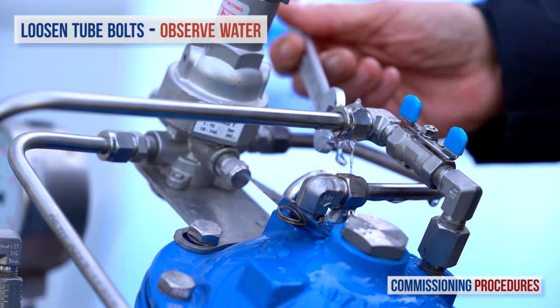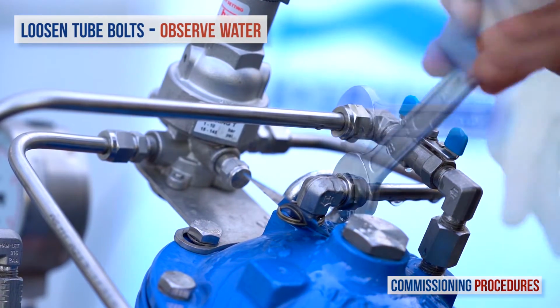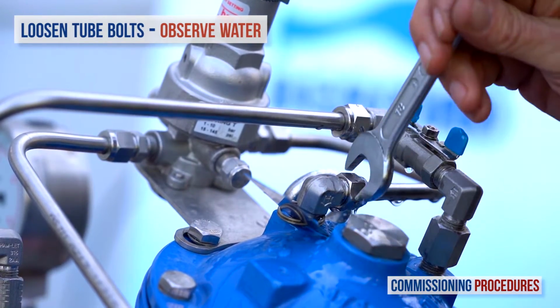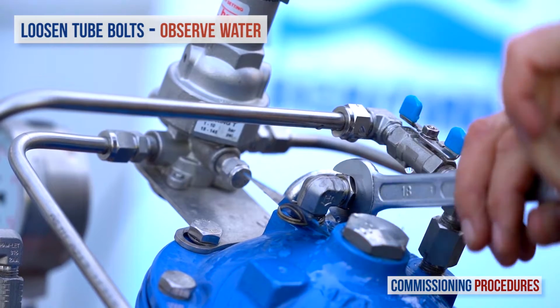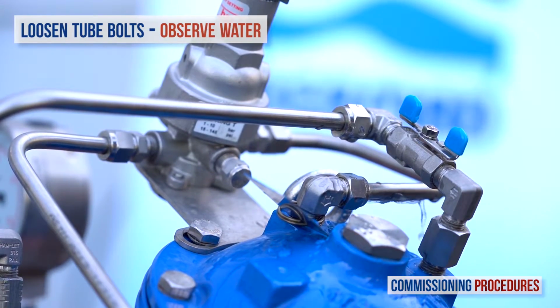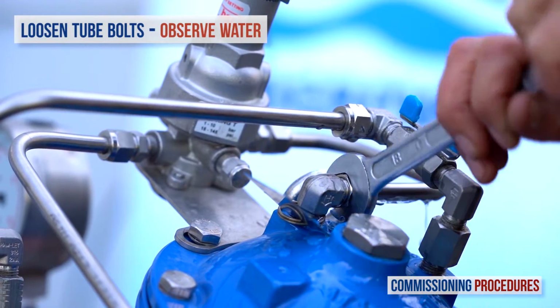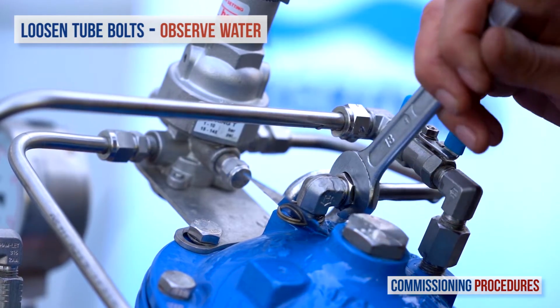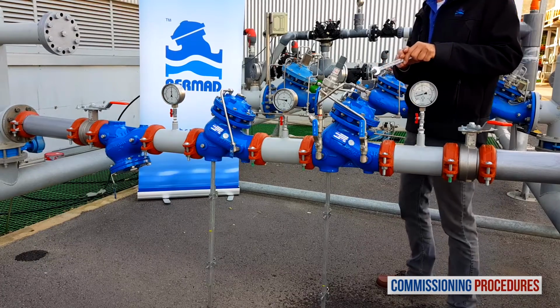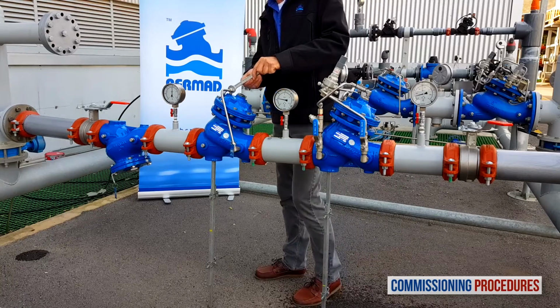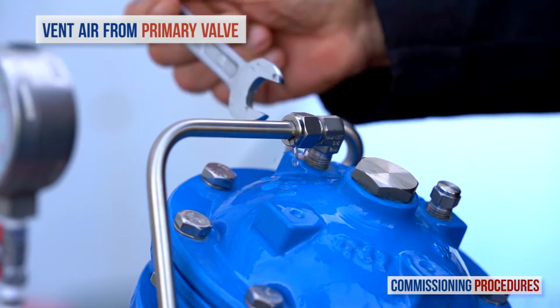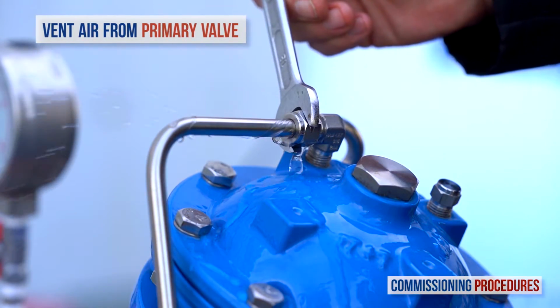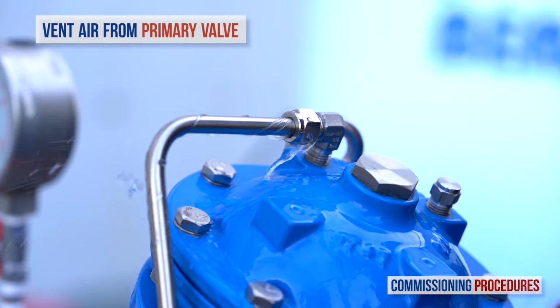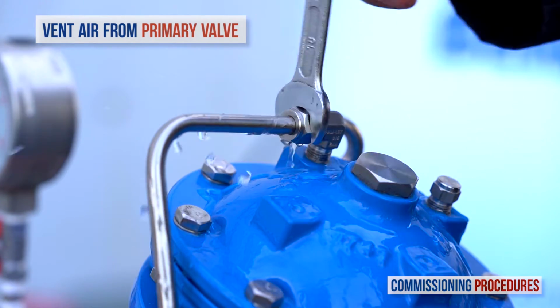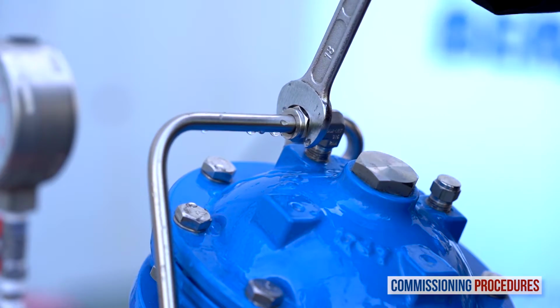You may notice air exiting the eyebolt. As soon as you get a flow of water without air, retighten the tube fitting eyebolt. Repeat the same procedure on the primary valve. This completes the commissioning procedure.